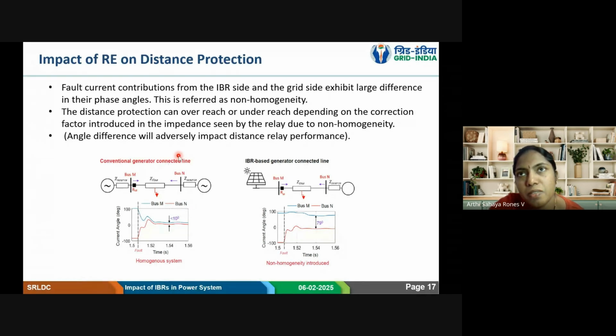One more thing we are observing is that due to the lack of short circuit contribution, a voltage collapse condition happens, and the distance relay is picking up under those conditions. Even though the current is not high, when the voltage becomes very low, the characteristics come inside the impedance loop. So those are typical examples of the impact of RE on the distance protection. This variation in the angle between the grid end and the IBR end, we call non-homogeneity. Much work is being carried out in this regard. One of the adaptive approaches is the zero sequence based one.